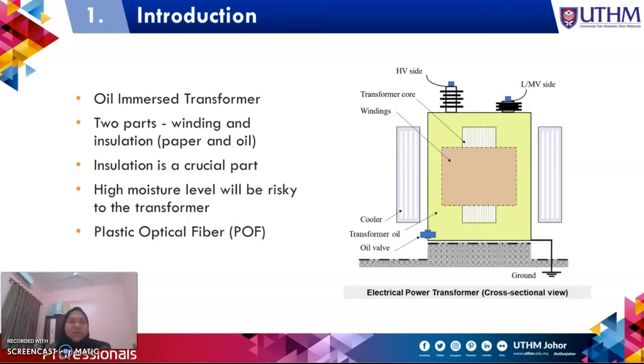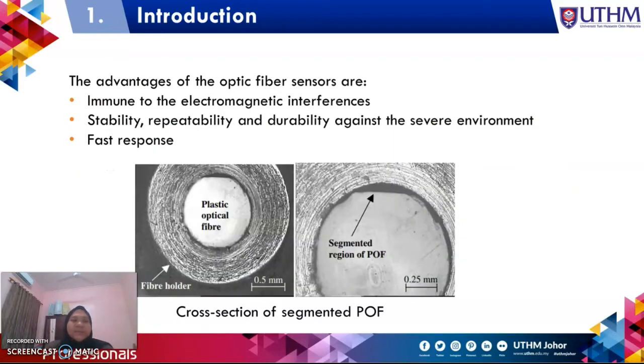In this case, we're going to use a plastic optical fiber, simply called a POF sensor, to measure the moisture content of the transformer oil. The advantages of the optical fiber sensor, why we use this type of sensor, are that it is immune to electromagnetic interference, it has stability, repeatability, and durability against severe environments, and it has a fast response.